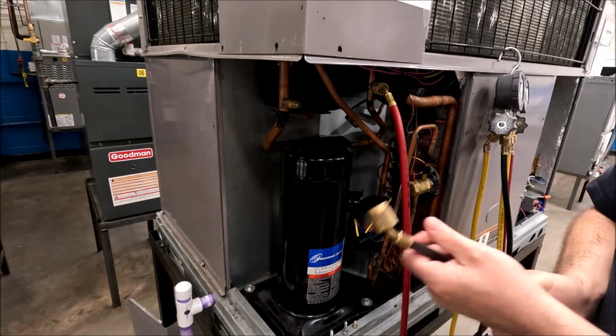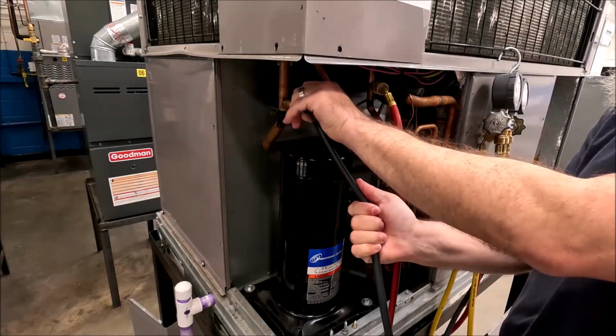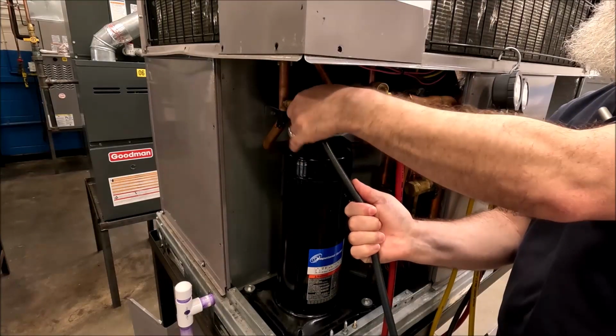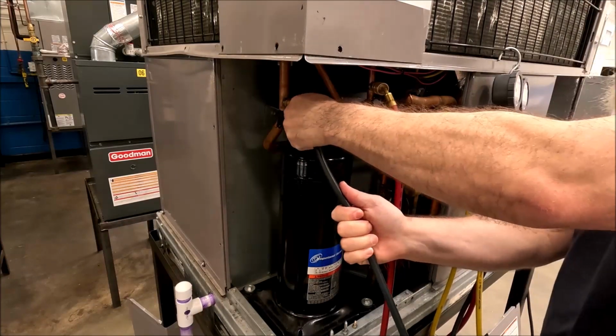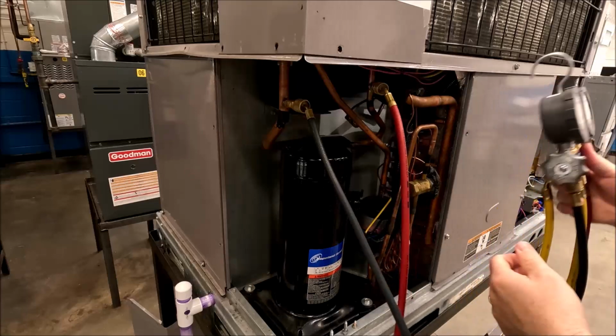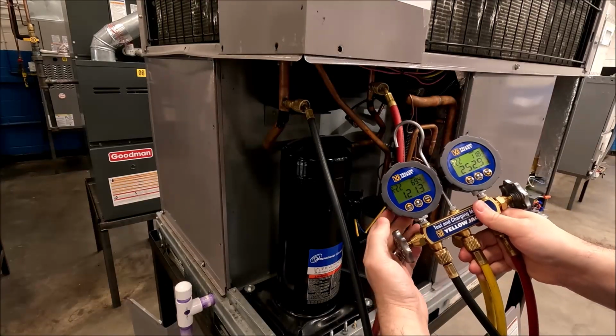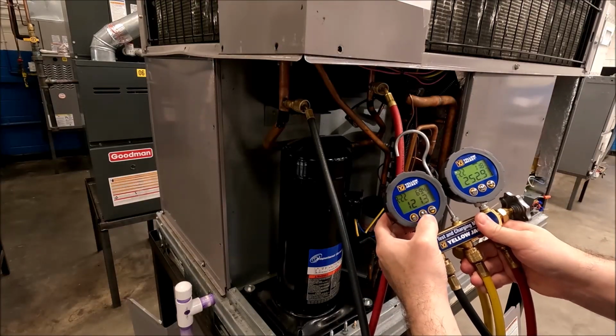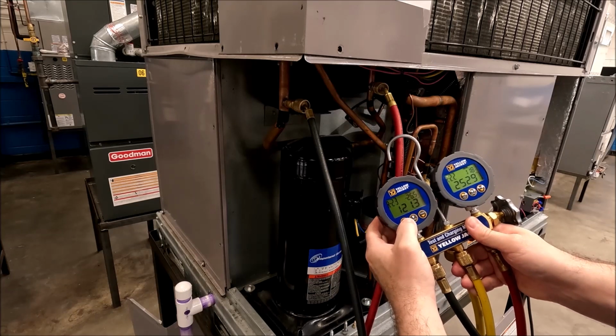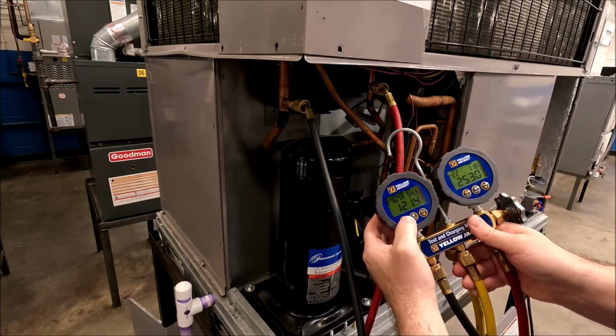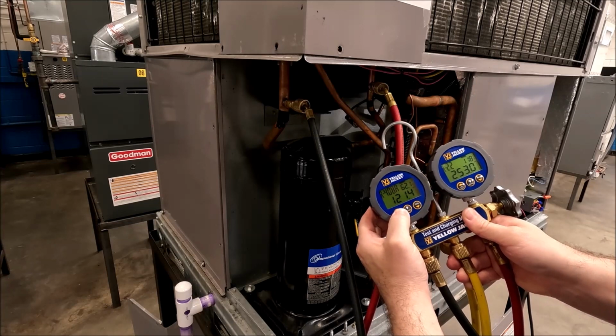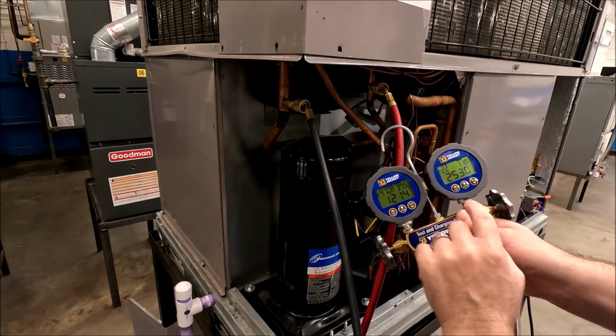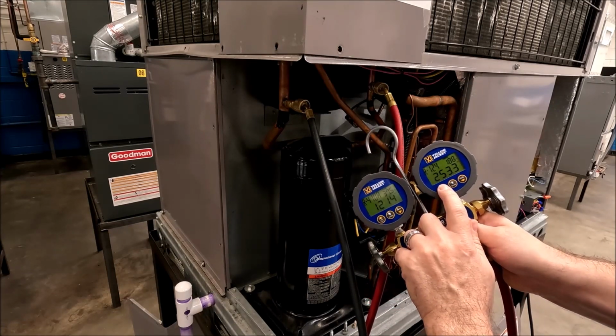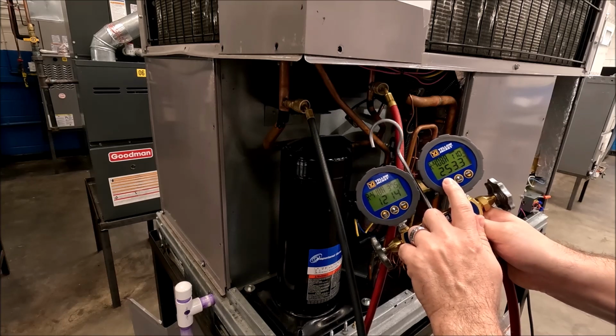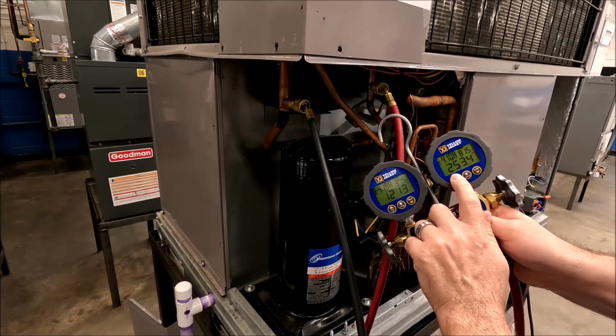And this is where we're going to hook up our low side. I've got a set of Yellow Jacket digital gauges here, and what I've got to do is get to the right refrigerant, which is R410A for this unit. So I'm going to cycle up. Oh, too far. There we go.